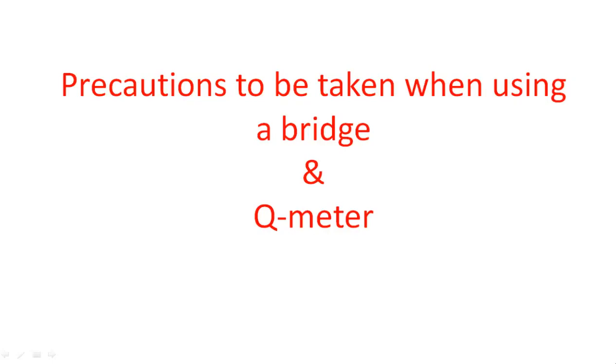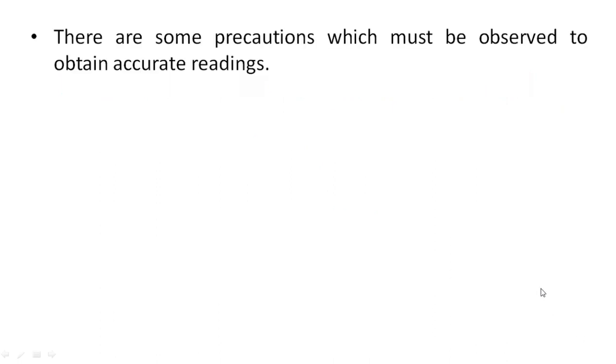In this video, I am going to explain the precautions to be taken while using a bridge, as well as another important concept: the Q meter. We need to consider precautions when measuring bridge components like capacitance and inductance, especially in AC bridges. These problems may not occur in DC bridges because the issue is due to lead capacitance and lead inductance.